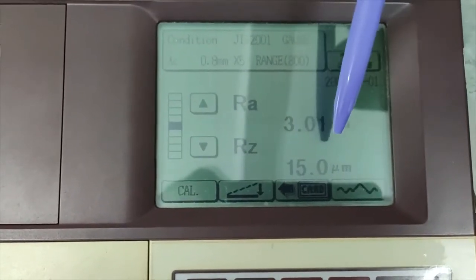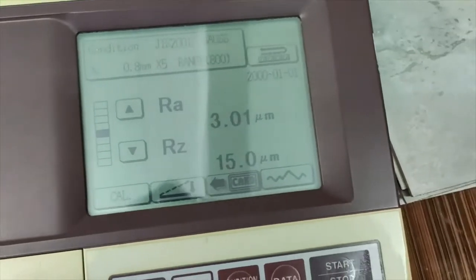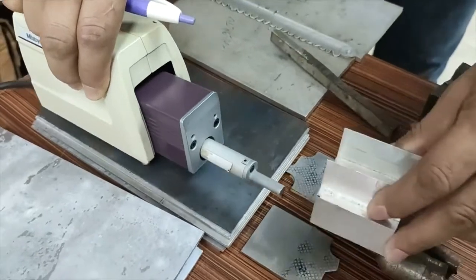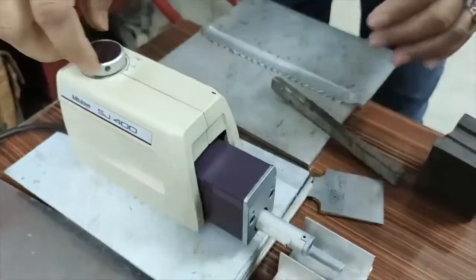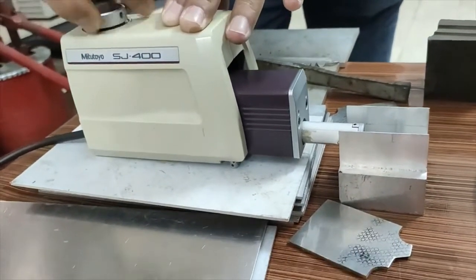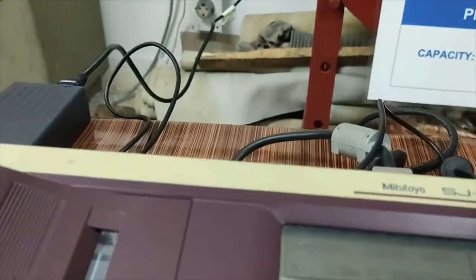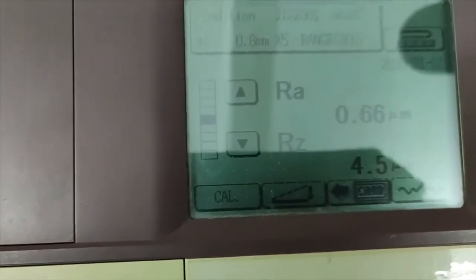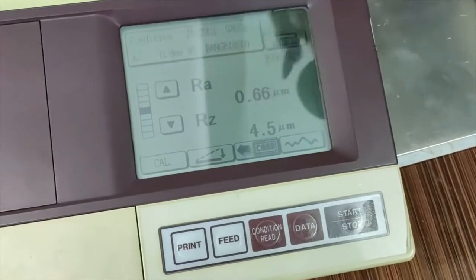This is our result. Ra is roughness average, 3.01 micrometer, and total roughness Rz is 15.0 micrometer. The Ra value formula I will show you later. Like this way you can measure the milling surface of aluminum by adjusting each side. Like this you just adjust it whether it is touching or not. You can see it is touching. Press start button again. This surface Ra value is 0.66 micrometer and Rz value is 4.5 micrometer.